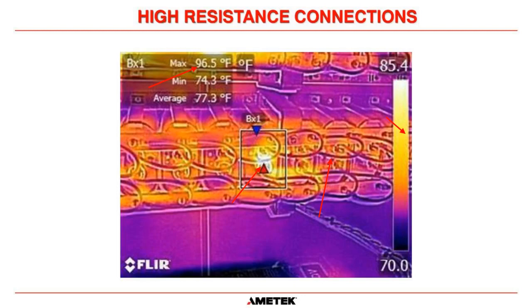So what the field service technician did was he powered the system down and had a look to see what was wrong with the connection. And he found the connection wasn't connected properly to the capacitor spade terminal. What he found was it had been installed between the plastic collar and the spade terminal itself.